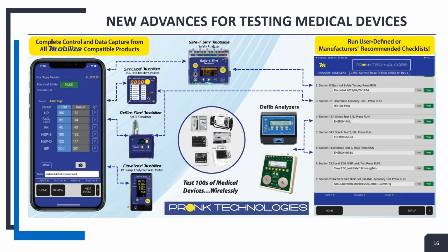So here, yes, we want to connect the electrical safety analyzer to the defibrillator. We've done that here. It wants you to connect your defibrillator to it. The Zoll X does not require a ground resistance test. The R's do, but the X does not require a ground resistance test. We need to do an applied parts leakage test on everything. So we need to connect our ECG leads, and we also need to connect our therapy cable to it as well. The therapy cable is considered an applied part, so you need to connect that to your electrical safety analyzer, to the applied parts section here.